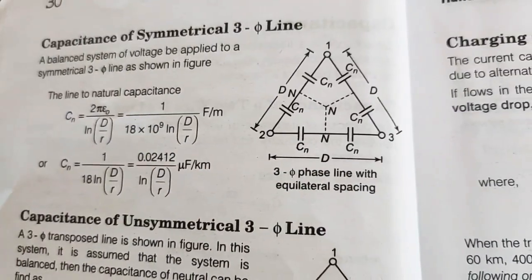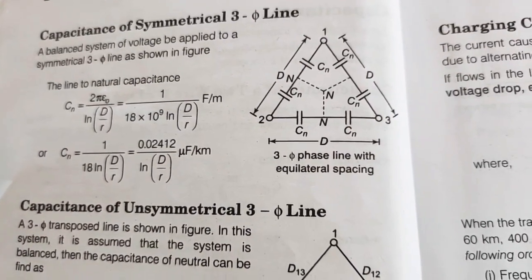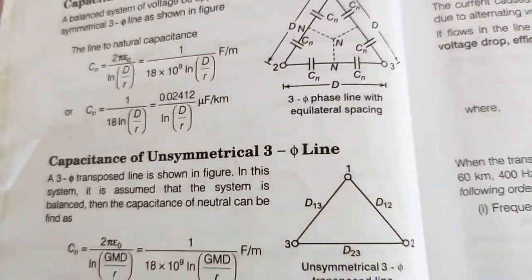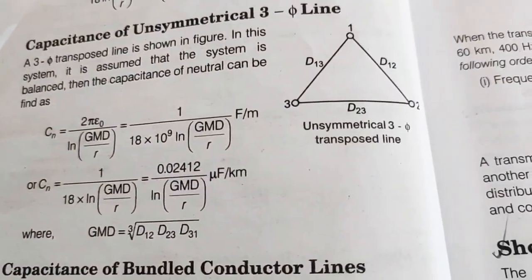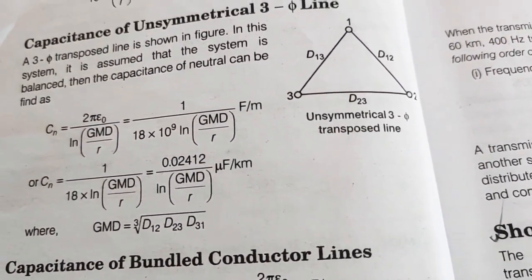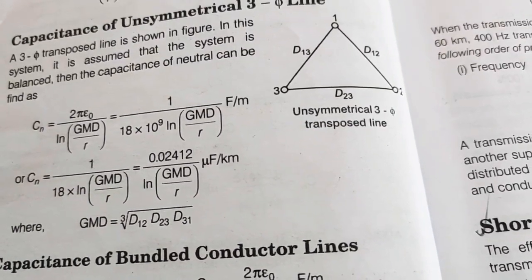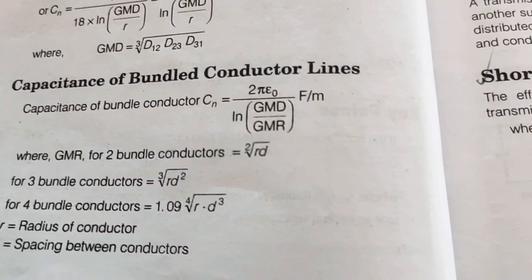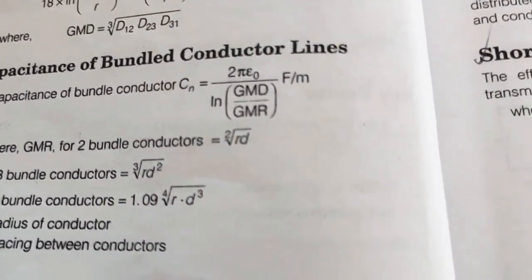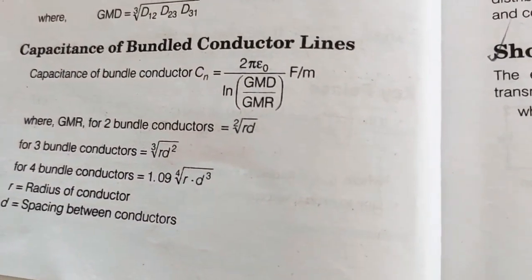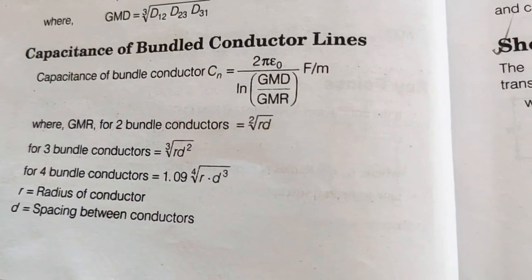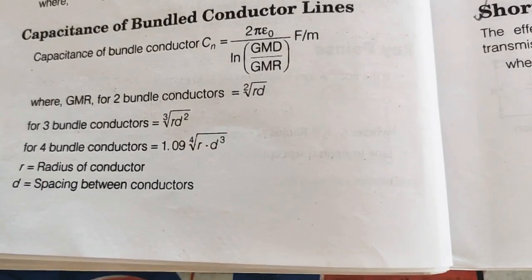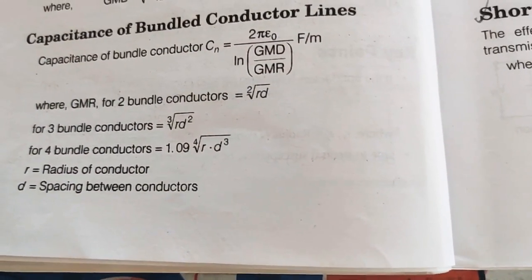Capacitance of a symmetrical three-phase line: Cn equals 0.02412 divided by ln(D/r) microfarads per kilometer. For an unsymmetrical three-phase line, GMD equals the cube root of D12·D23·D31, and Cn equals 0.02412 divided by ln(GMD/r) microfarads per kilometer. Capacitance of a bundled conductor: Cn equals 2 pi epsilon-naught divided by ln(GMD/GMR) Farads per meter, where GMR for two bundled conductors is the square root of r·d, for three conductors is the cube root of r·d-squared, and for four conductors is 1.09 times the fourth root of r·d-cubed.